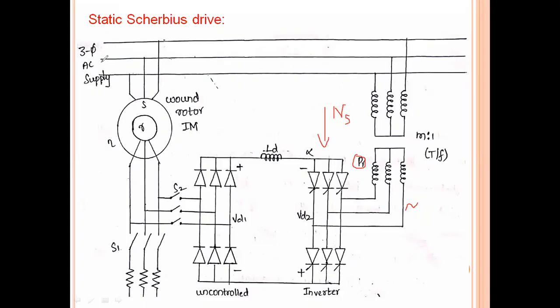And similarly, when we compare with the stator voltage control or stator frequency control also, there also we don't have any recovery schemes. So when compared with the stator control also, the recovery schemes, which is the static Scherbius drive or Kramer drive, will produce higher efficiencies. So rotor control of induction motor will produce higher efficiencies when compared with the stator control also.